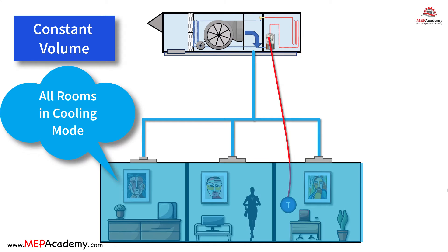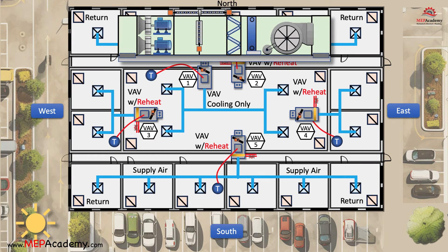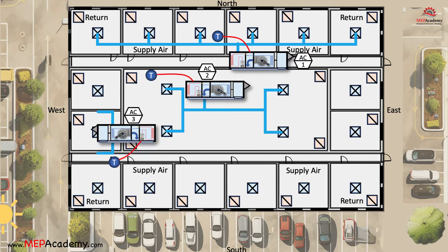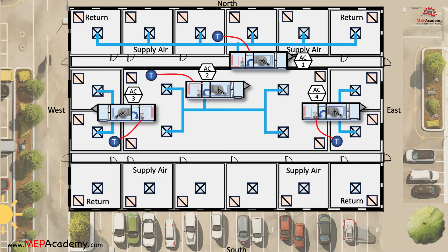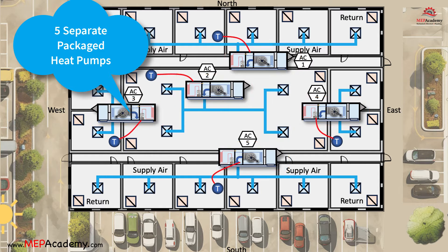They are less suited for buildings with diverse thermal loads. As you can see in this diagram, all rooms have to be in either cooling or heating mode — there is no option for one room to be in cooling while another is in heating mode. The VAV system can use one large air conditioner, whereas to keep the same five zones with constant volume, you would need a separate package constant volume AC unit for each zone, requiring five separate heat pumps.